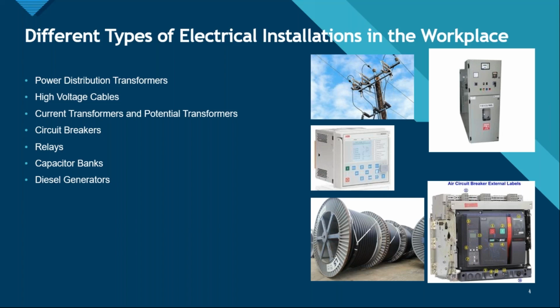So that's what the current transformers and potential transformers do, right? Stepping down maybe thousands of amperes of current to maybe 1 ampere or 5 amperes, right? That's the range, that's the ratio for a current transformer or a potential transformer. So in case any hazards happen around that, that high rating of current might be released. And around current transformers and potential transformers, there is a high risk of arc flashes or even arc blasts that can happen. So we'll be talking about those things as well, how the current transformers work and the hazards related to them.